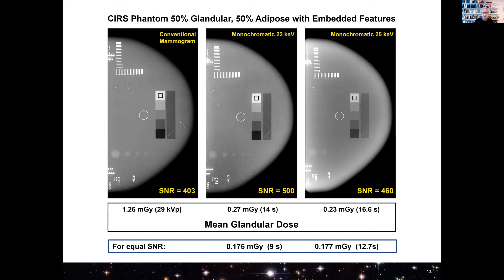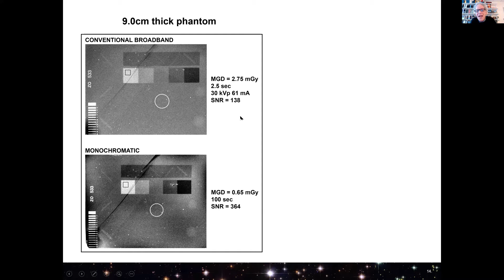We go to the other extreme. We've made a 9 centimeter thick phantom and measured images with the conventional broadband machine and our unconventional monochromatic system. Here we used a 3 by 3 millimeter square only because we had a crack in the top phantom, so we just made it a little bit smaller. We'll talk about that later. But for the conventional machine, to give a signal to noise corresponding, in this case, to 138, it had to raise the dose to 2.75 milligray. With only 0.65 milligray of dose, we got a signal to noise that's more than twice the value.